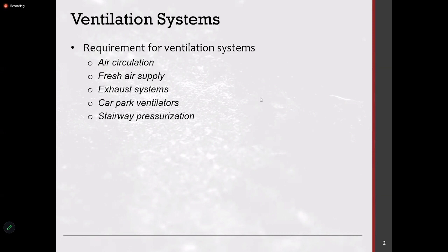Then there is some amount of CO2 which gathers inside the room, and the CO2 levels inside the room increase because of human presence; otherwise it's not a problem. So fresh air supply is not required if only machines are there, because there are no breathing elements. But if human presence is there, then a certain amount of CO2 is generated, the CO2 level goes up, and maybe the oxygen level also goes down, because it is a fully sealed space, like a fridge. So in that case, there could be certain other issues arising, which you need to cater to.